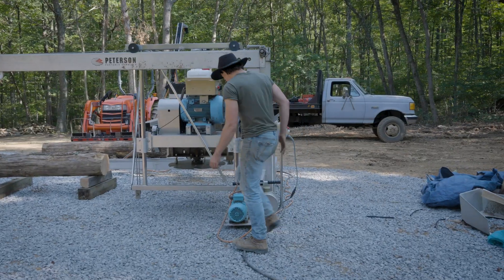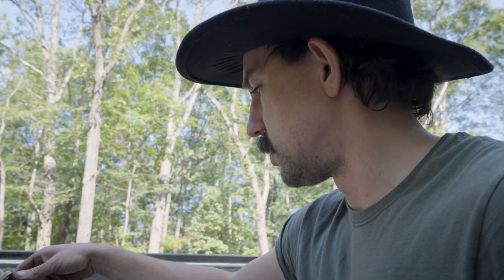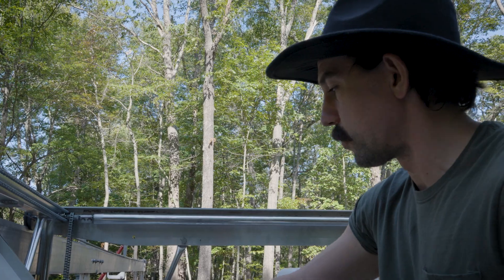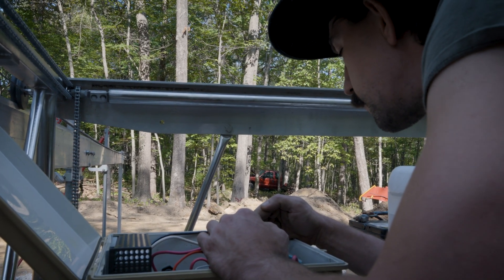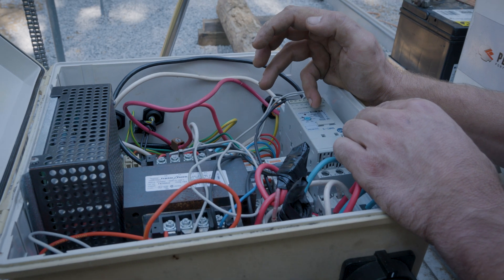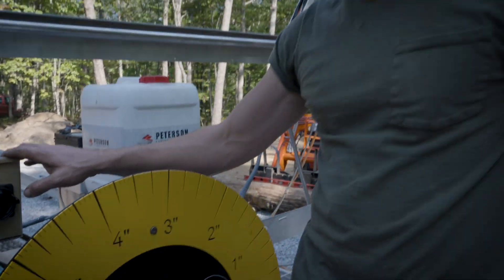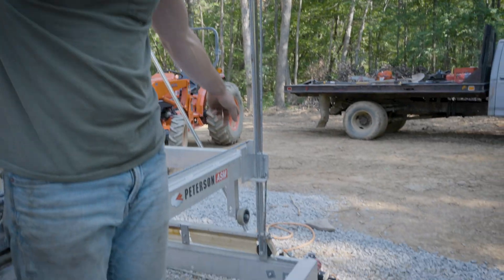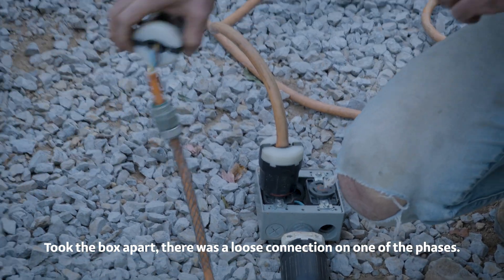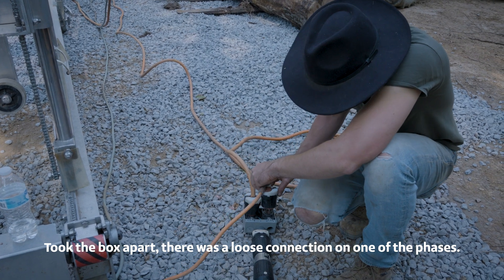It's not spinning, it's humming. We're just going to turn on the big motor to see if it's out of phase. The small drive motor's humming but it's not jammed. The bearing and the pulley can all spin freely, so I think it might be a phase issue. If this runs perfect, then we have a problem with the wiring going to that motor. It says phase loss. So we'll get the multimeter — one of the phases might be open, meaning somewhere in the wiring. Maybe when I disconnected and fixed that plug, I messed it up. We were missing a phase. Sure did — we were missing a phase.